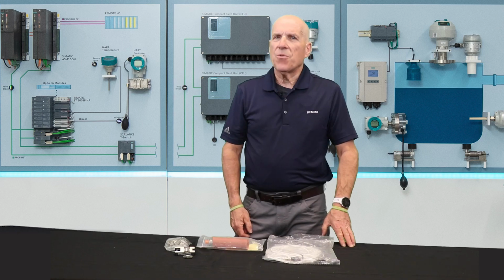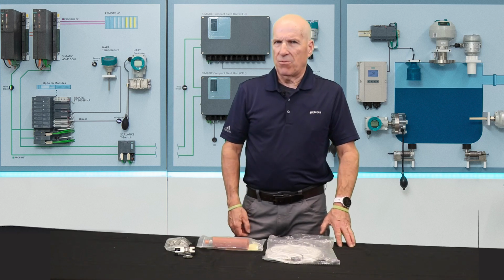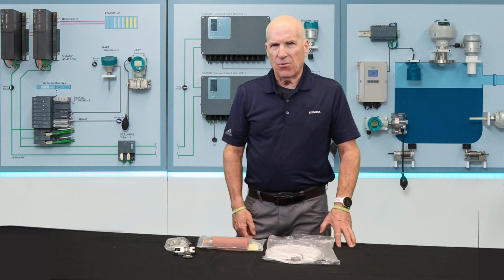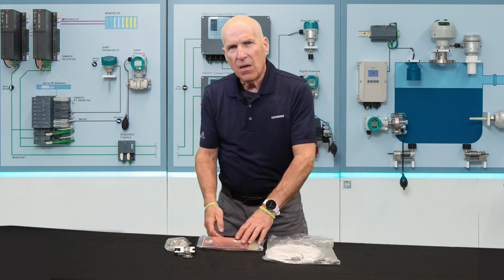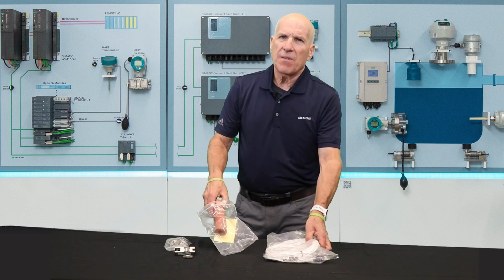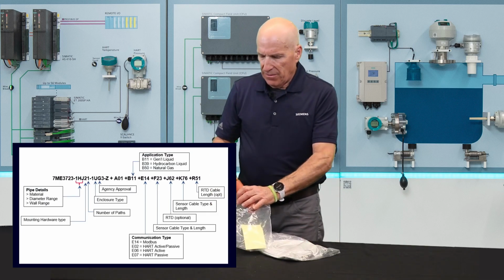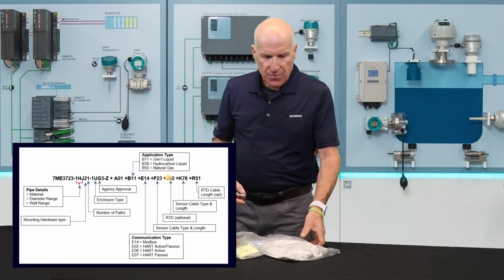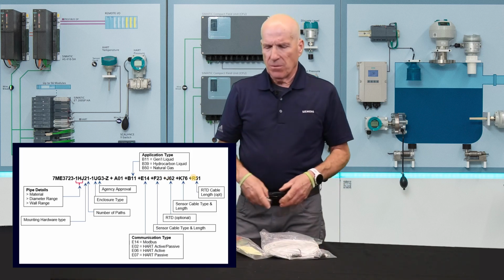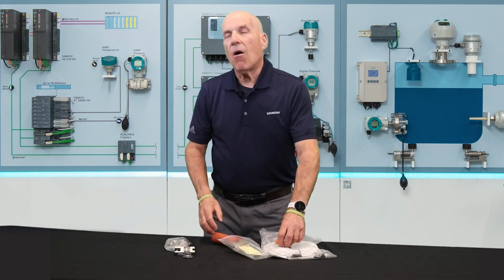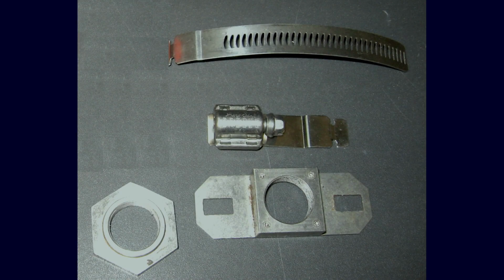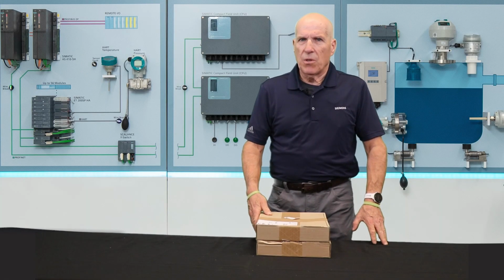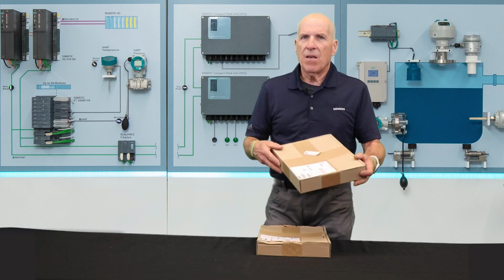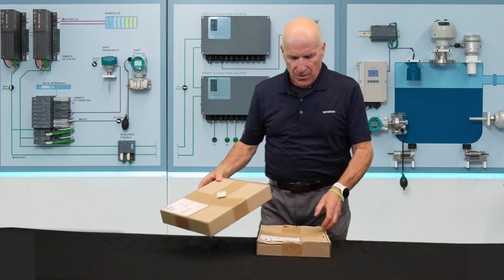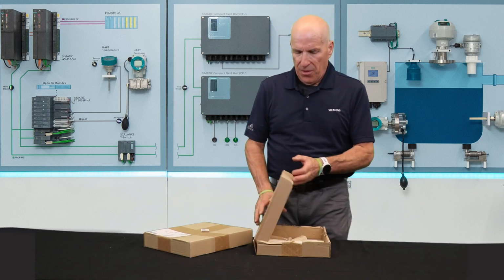Certain variants of the FS230 system will include a couple of additional accessories. Hydrocarbon liquid and natural gas transmitters typically include an RTD, along with an RTD cable for temperature measurement. These are identified by the J for the RTD and the R for the RTD cables. Along with the RTD and cable is a mounting rig for the RTD to strap it onto the pipe. All natural gas transmitters will also be delivered with a damping film kit, sized for the flow sensors provided. There's one for each path.